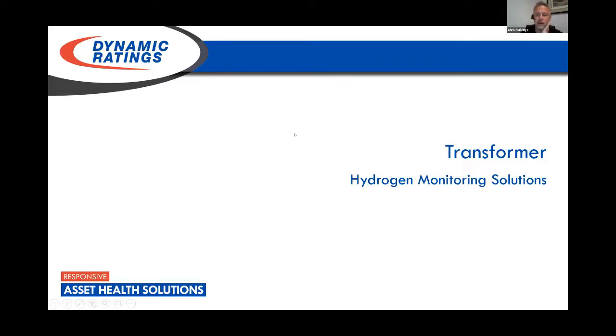Today, we're going to look at hydrogen monitoring solutions, and this is primarily concerning network type transformers found in vaults. As Randy mentioned, I come from Memphis Light, Gas, and Water. Actually, we have the oldest network system in the country. It was established in 1907 was when they first went into service with it there. So we had quite a bit of older equipment that we were using, and we were starting to see a high level of failure. So at that point, I was tasked with trying to find some solution to monitor these, to prevent these failures. So that was kind of what got me started down the path of looking at monitoring of network transformers.